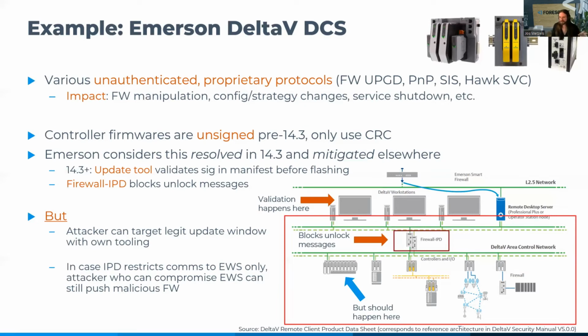Since controllers can be software locked, certain engineering operations can't take place until you unlock them by sending an unlock message over one of these protocols. The firewall IPD drops this message, so it doesn't go from the workstations or servers to the controllers unless a physical override is initiated on the firewall IPD or the controllers themselves. So technically, this is a good measure to reduce risk in a certain manner.